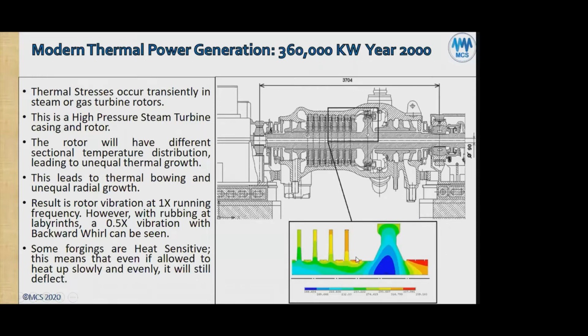Anytime you see the higher differential temperatures, it means there's thermal stresses, but also unequal thermal growth. Leads to thermal bowing and unequal radial growth. Result is rotor vibration at 1 times running frequency. However, if the bow is excessive, you're going to get a rub at the labyrinths. And there you're going to see a 0.5x vibration, or it could be a 0.49x vibration with backward whirl. A rub will never cause forward whirl.